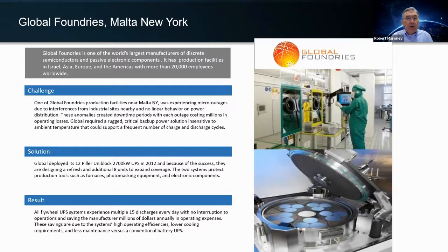It's been a production system for them. In that particular case, there's about 12 megawatts of load on the Piller rotary UPSs, providing that protection for them. The systems are run at about 75% of load, and all systems are under load at all times. And if there were to be a failure of a system, they have redundancy built into the system as well.